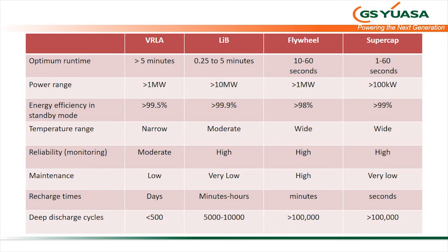Energy efficiency, just on float, not talking about round trip efficiency. They're all in similar regions, but flywheels do waste more energy to keep them cool, keep the vacuum running, keep them spinning. Lithium ion is definitely the highest, because you're not charging at all. There's no float current. Once they're charged, they're charged. They're not taking any more energy after that. Temperature range, VRLA, it's pretty intolerant to temperature ranges if you want to get the optimum life. Lithium ion is less so. It's much more forgiving as your temperature goes up. So you don't need to run them at 20 degrees C. And the lifetimes are based on 25 to 30 degrees C normally, which can be the difference between compressor cooling and natural air cooling.